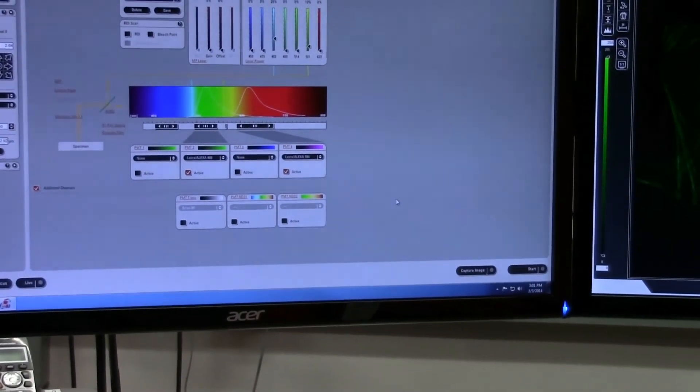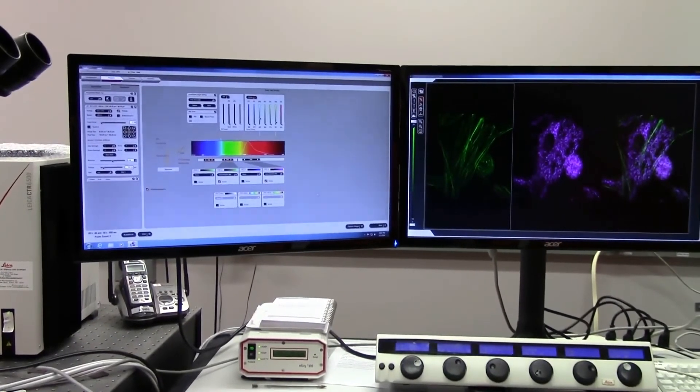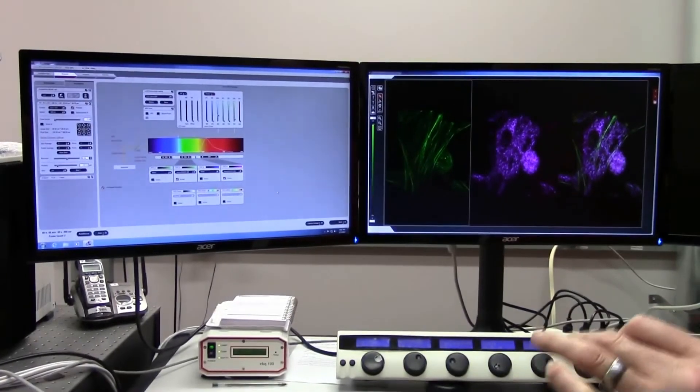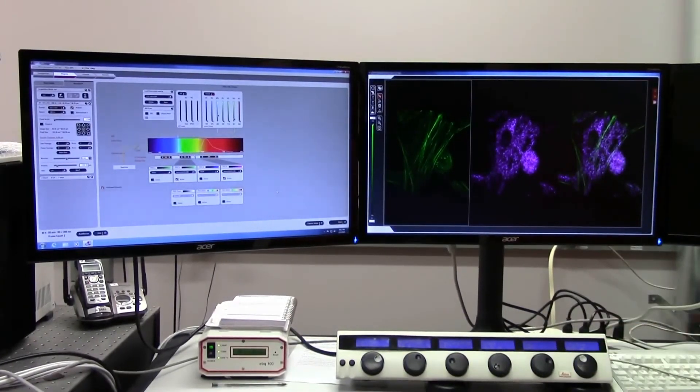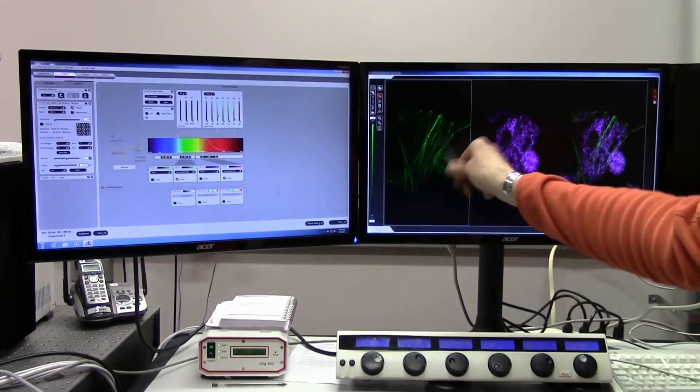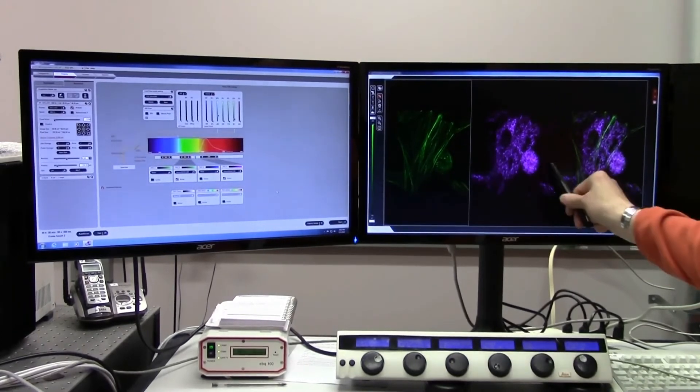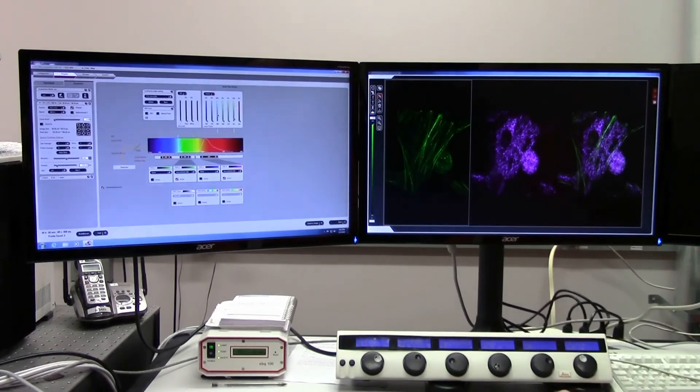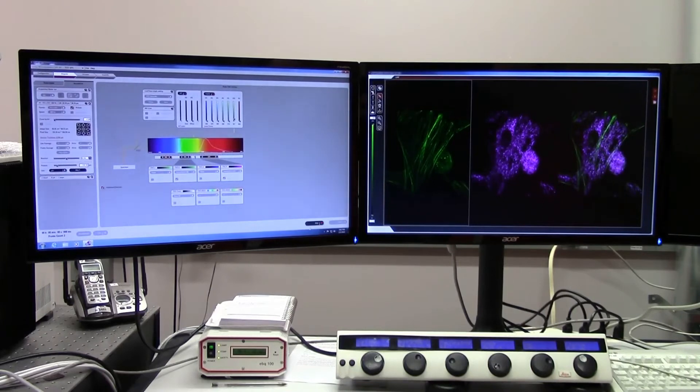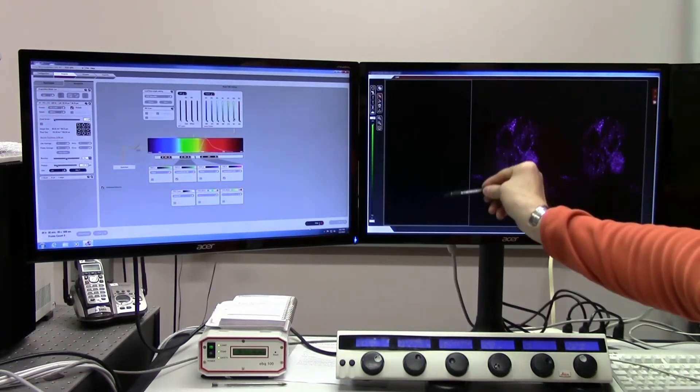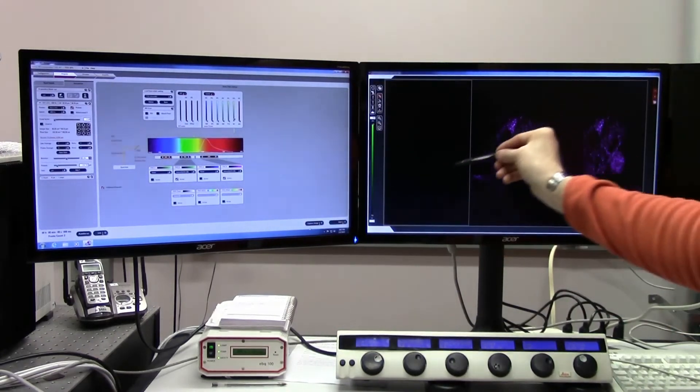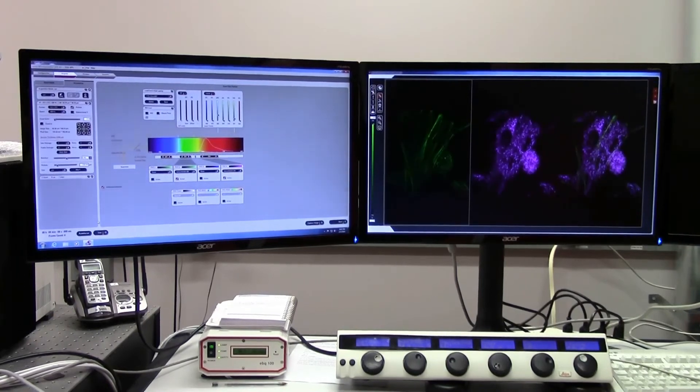There's a series of controls that you can put into place to give yourself some confidence that what you're seeing in two separate channels is in fact due to two separate signals and not signal leaking from one channel to another. For example, in this image, one way we can get an idea if there's any contribution of the green light into the red channel is to take the exact same image except turn off the green laser. We'll press capture image. What we'll see is that there's nothing now coming from the green channel because that laser has been turned off, and we can see if there's been any contribution into the red channel. We really don't see any.